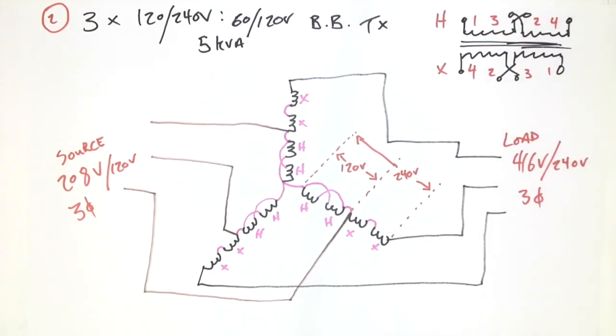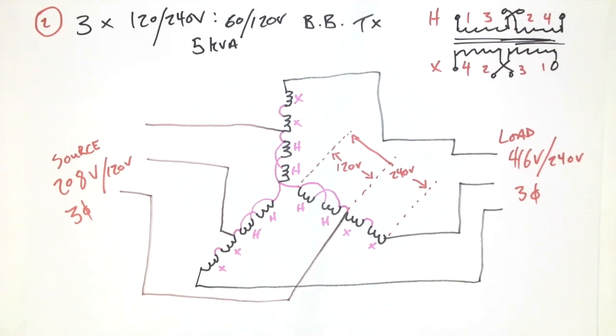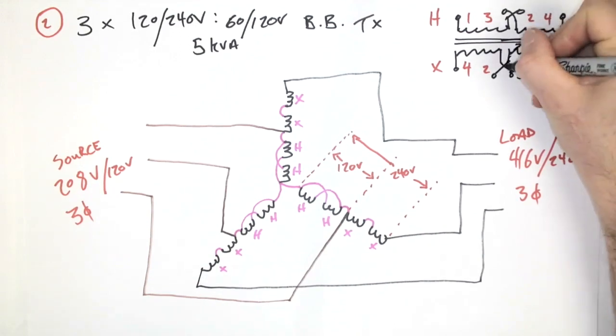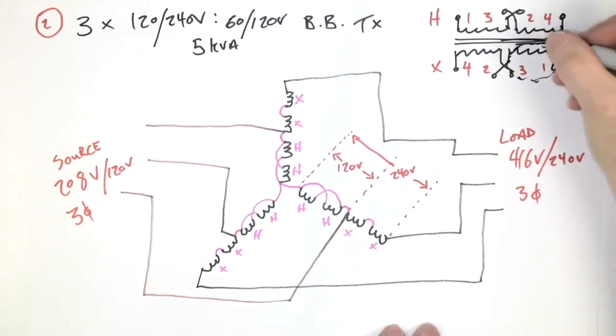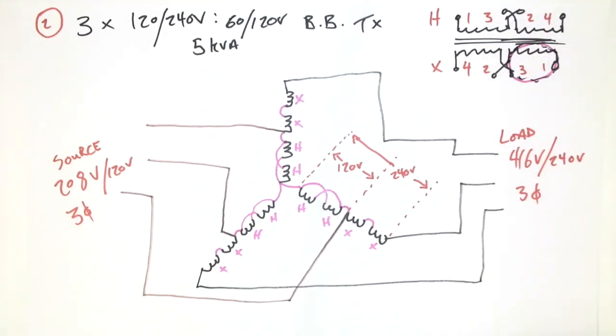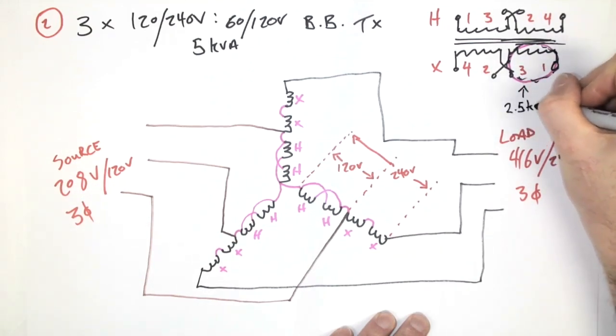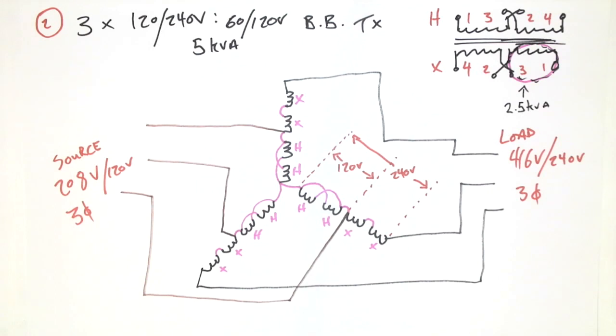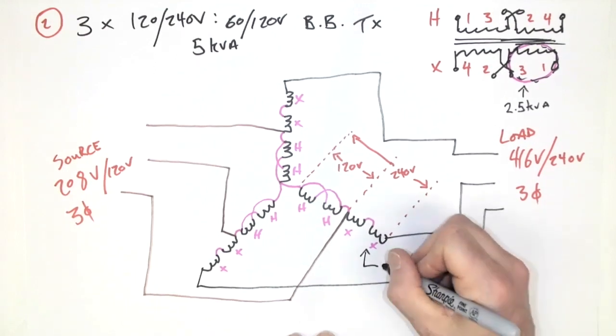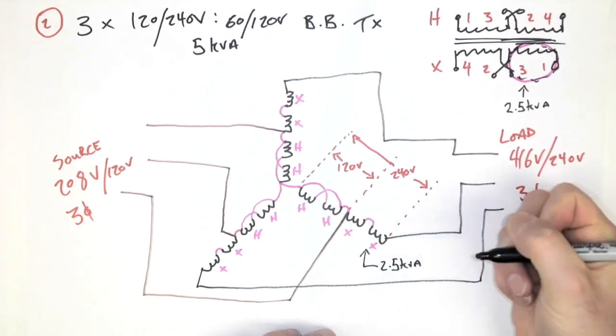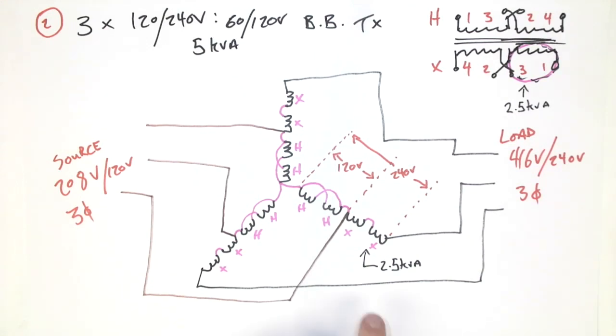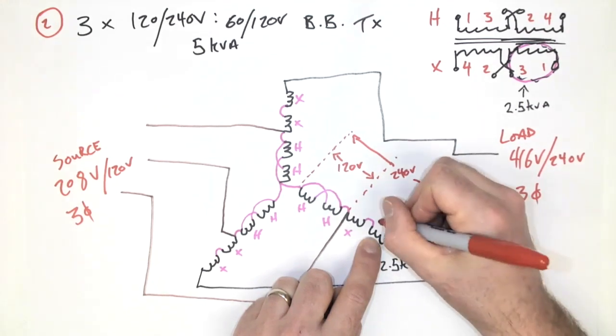All right, so now that we have that connection completed, we can go ahead and determine what is the total kVA of load that we can drive. Now remember from the previous example, I said one winding is equivalent to exactly half of the total kVA of the transformer. So this is 2.5 kVA. The next thing we're going to do is search for a series connection. Pretty simple. It happens to be on the load side again, but this is not always going to be the case. So it just happens to be for our situation. So we know that this is rated 2.5 kVA. And we also know that the voltage of this one individual winding here is actually 60 volts.